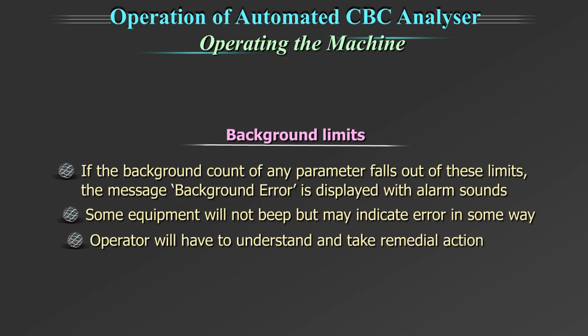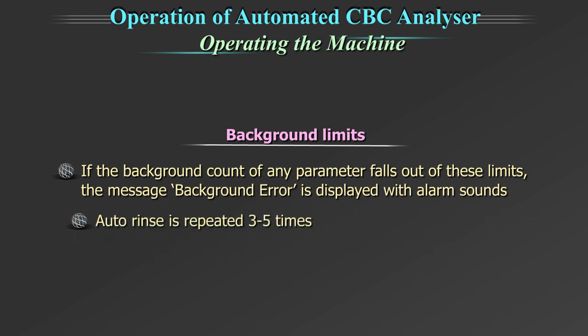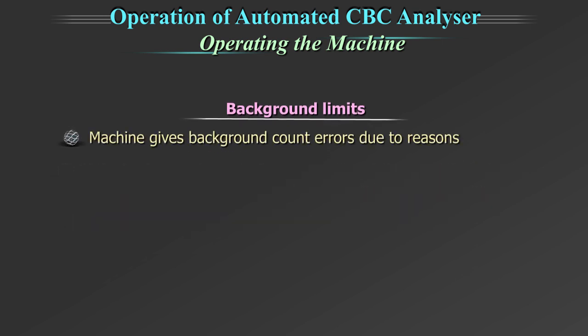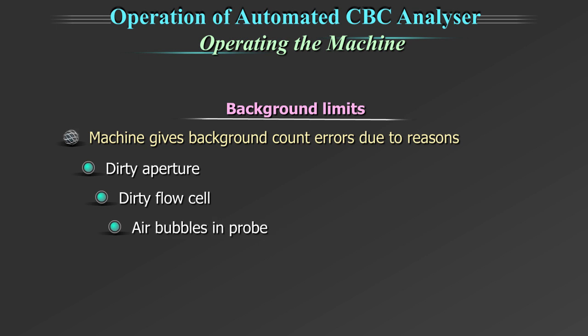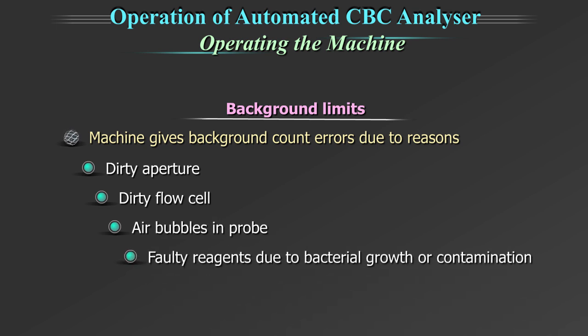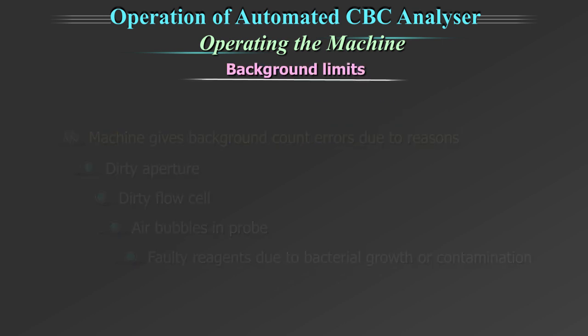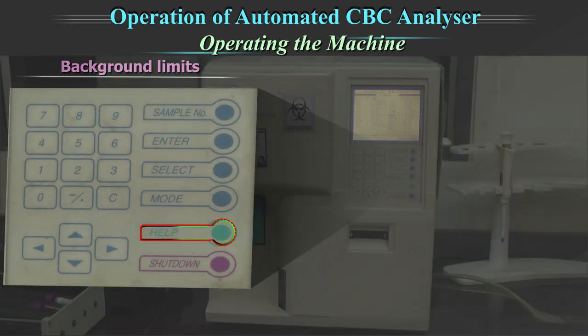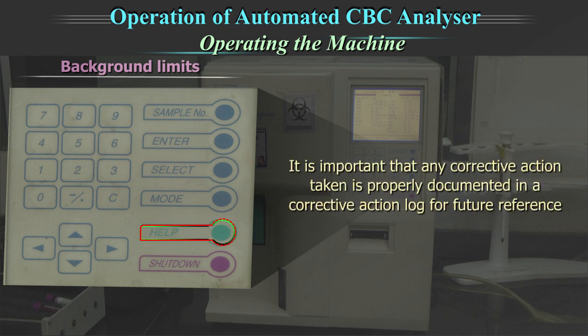If the background count of any parameter falls outside these limits, a 'background error' message is displayed with an alarm sound. Auto rinse should then be repeated 3–5 times. Machine may give background count errors due to dirty aperture, dirty flow cells, air bubbles in the probe, or faulty reagents due to bacterial growth or contamination. Please go through the help menu and take corrective action as displayed. It is important that any corrective action taken is properly documented in a corrective action log for future reference.